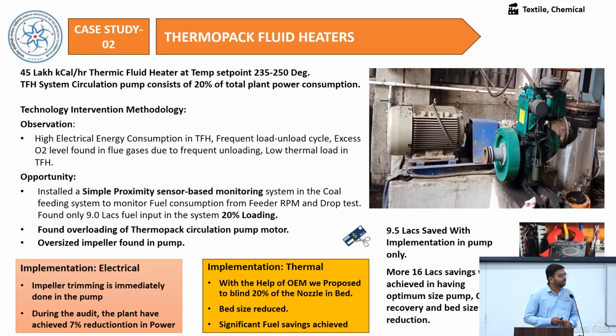It is a small scale industry, as we are doing the audits for MSMEs. This thermic fluid system is the major energy consumer in that textile industry. This textile industry has a demand of 285 kVA, and among the 285 kVA, almost 20% load is in only this system. Because this thermic fluid system was recently introduced in the industry, we observed that the thermic fluid pump is a totally oversized pump.